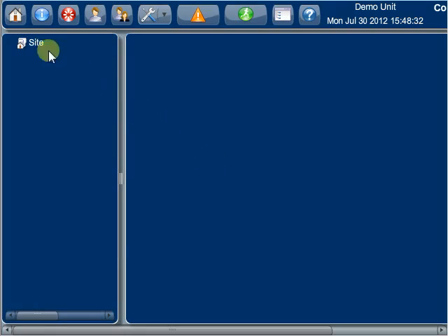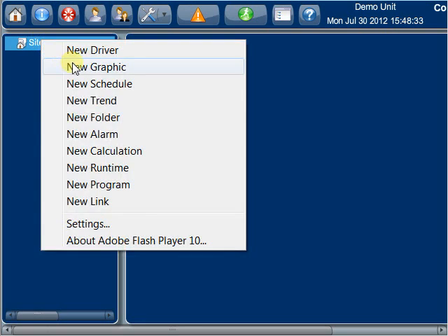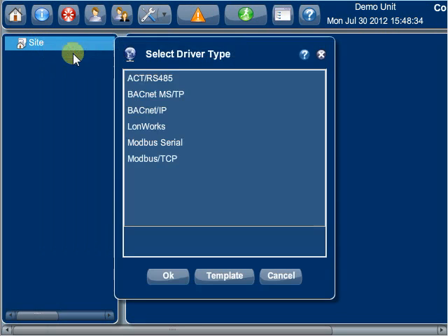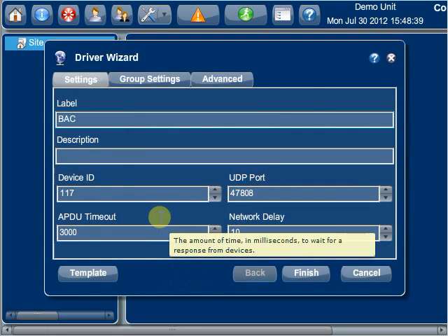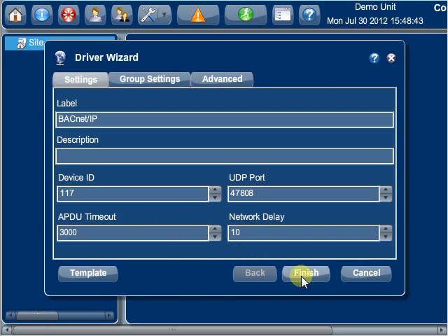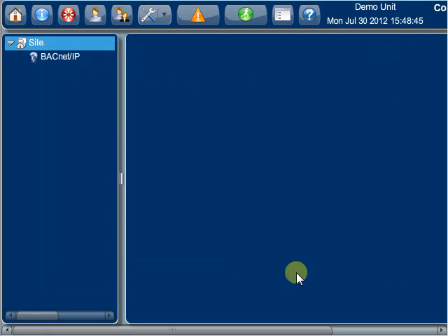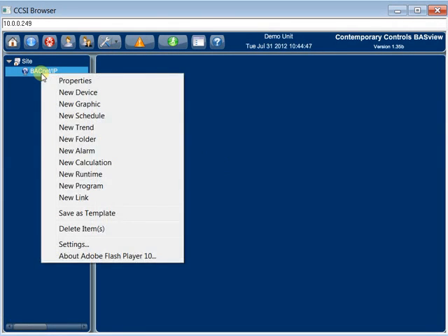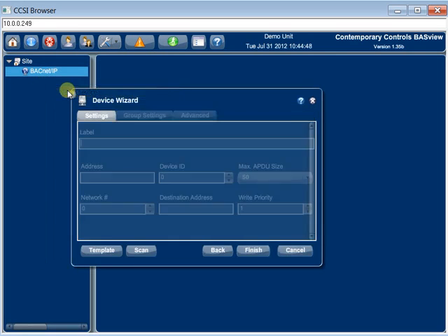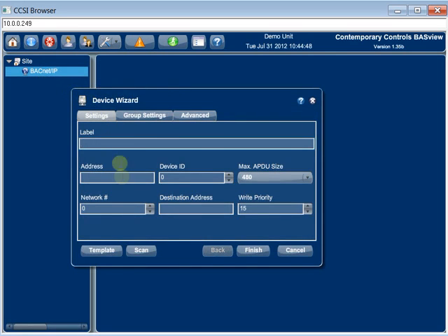The first step in the configuration process is to add a driver based on the network protocol being monitored. Physical devices are then added to the device tree under the appropriate network driver. Using a network protocol that supports discovery, such as BACnet, devices and their objects can be found with a simple scan command.